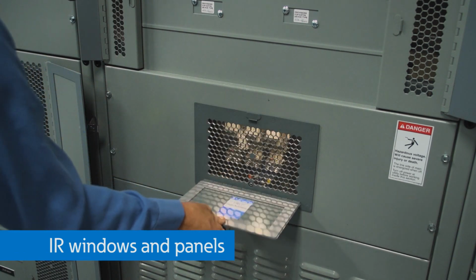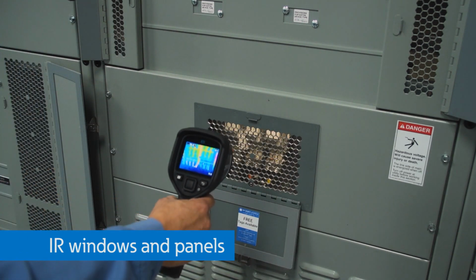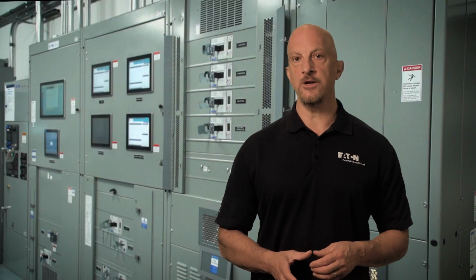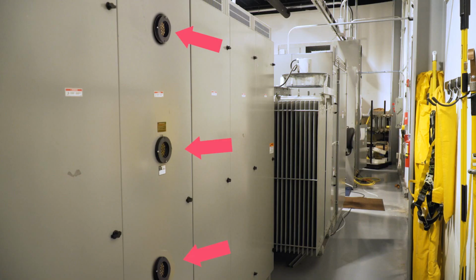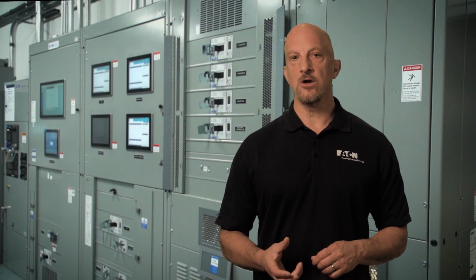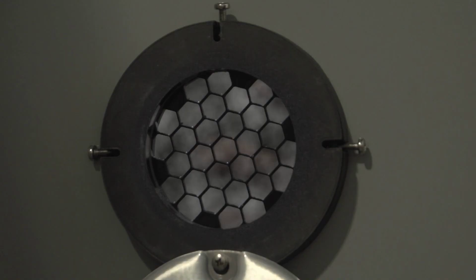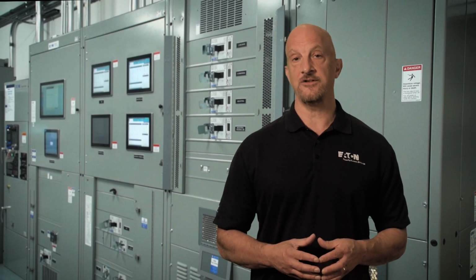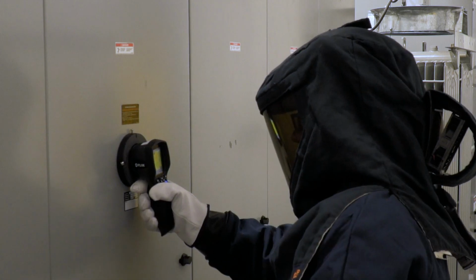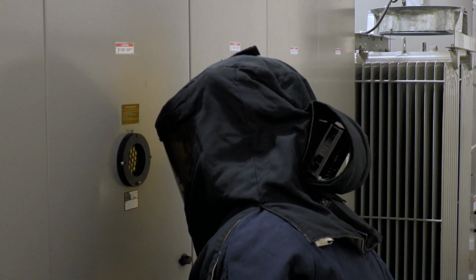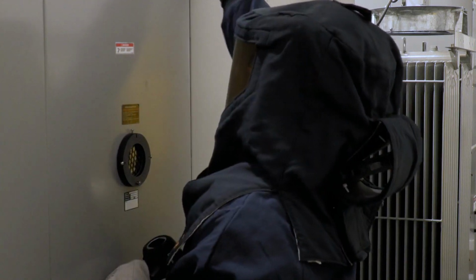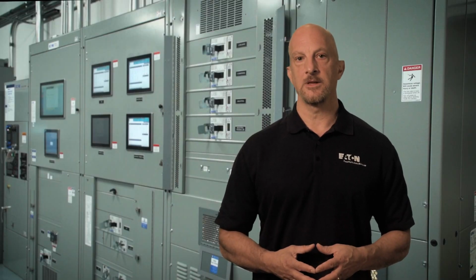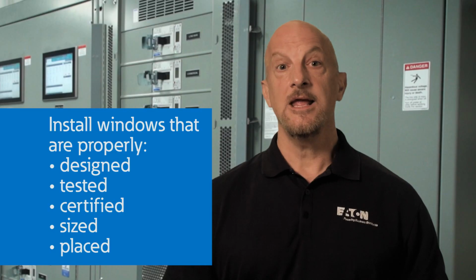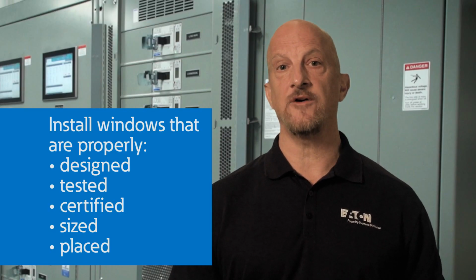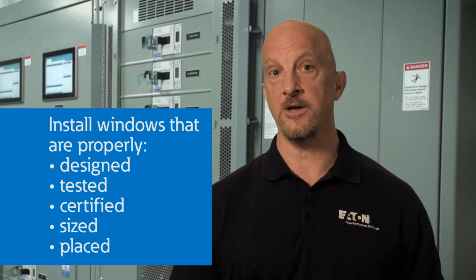Luckily, there's a fairly straightforward solution: IR windows and panels. Early versions of these windows were single, small, round windows that had to be strategically placed to see anything. In addition, they were opaque or had that frosted look that would allow an IR camera to see through, but you couldn't visibly see through it. The problem with this is that many times, if you found an issue with the thermal camera, you still needed to remove the cover to see what the camera was actually seeing. Today, there are much better options available.